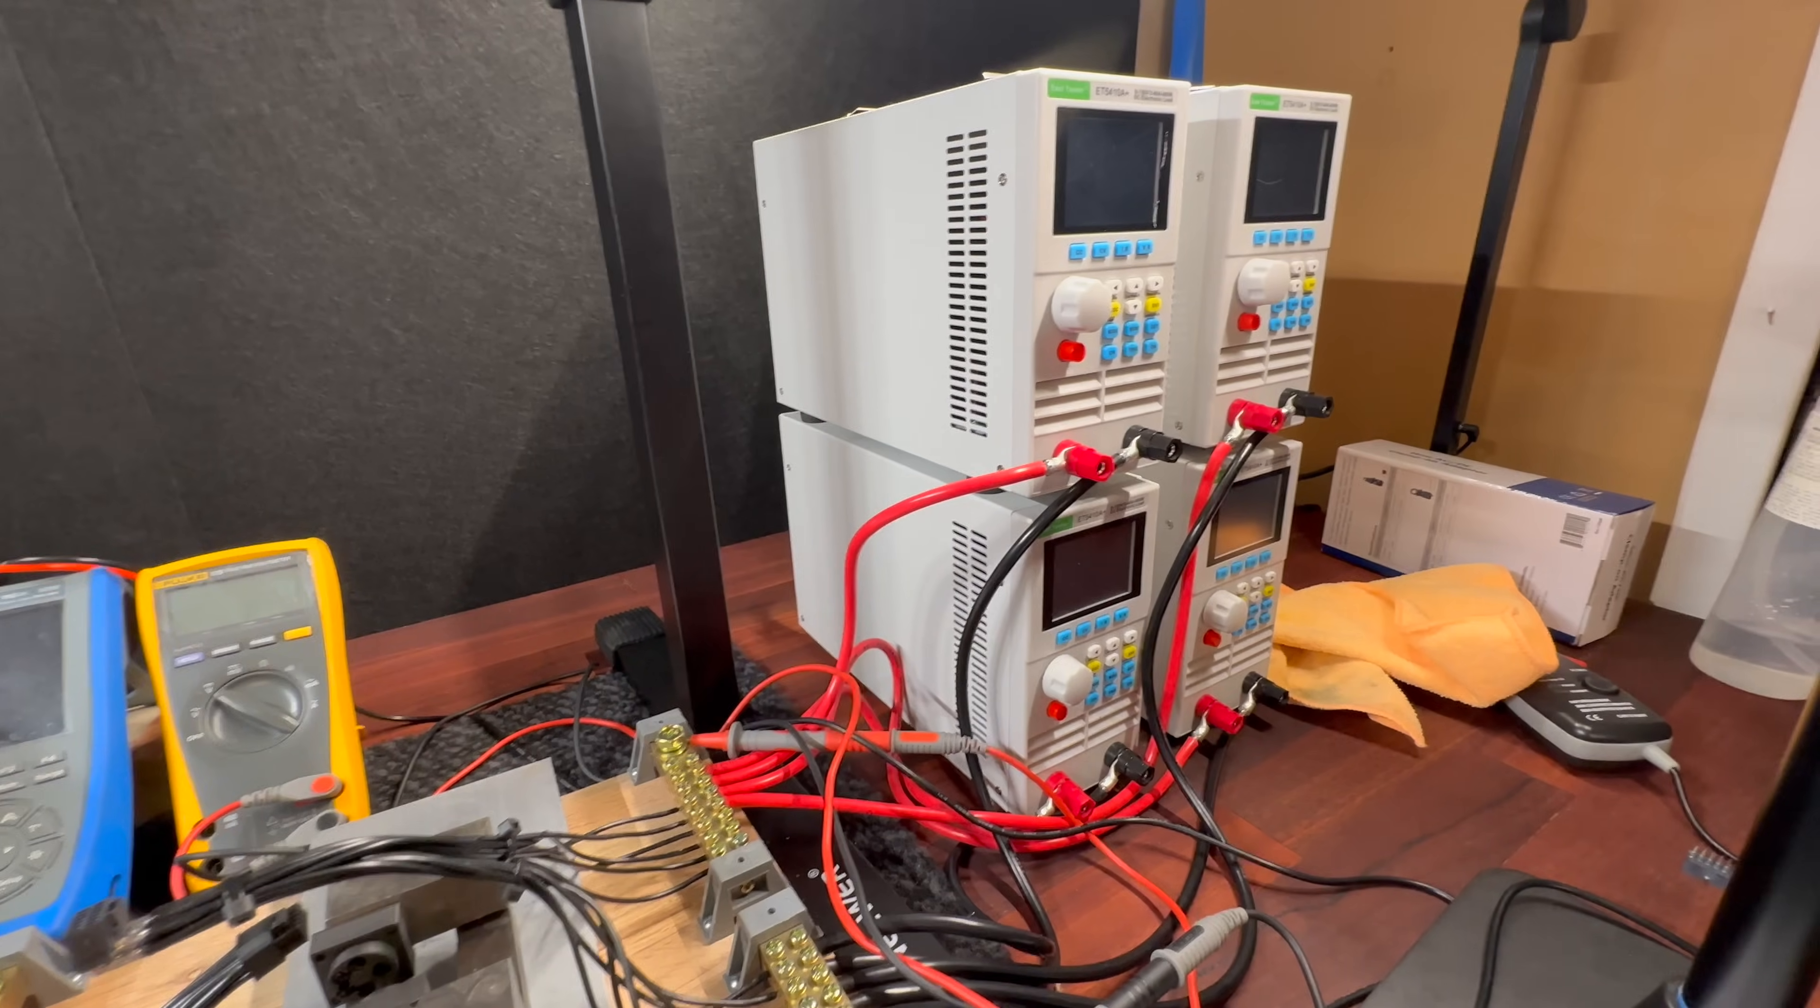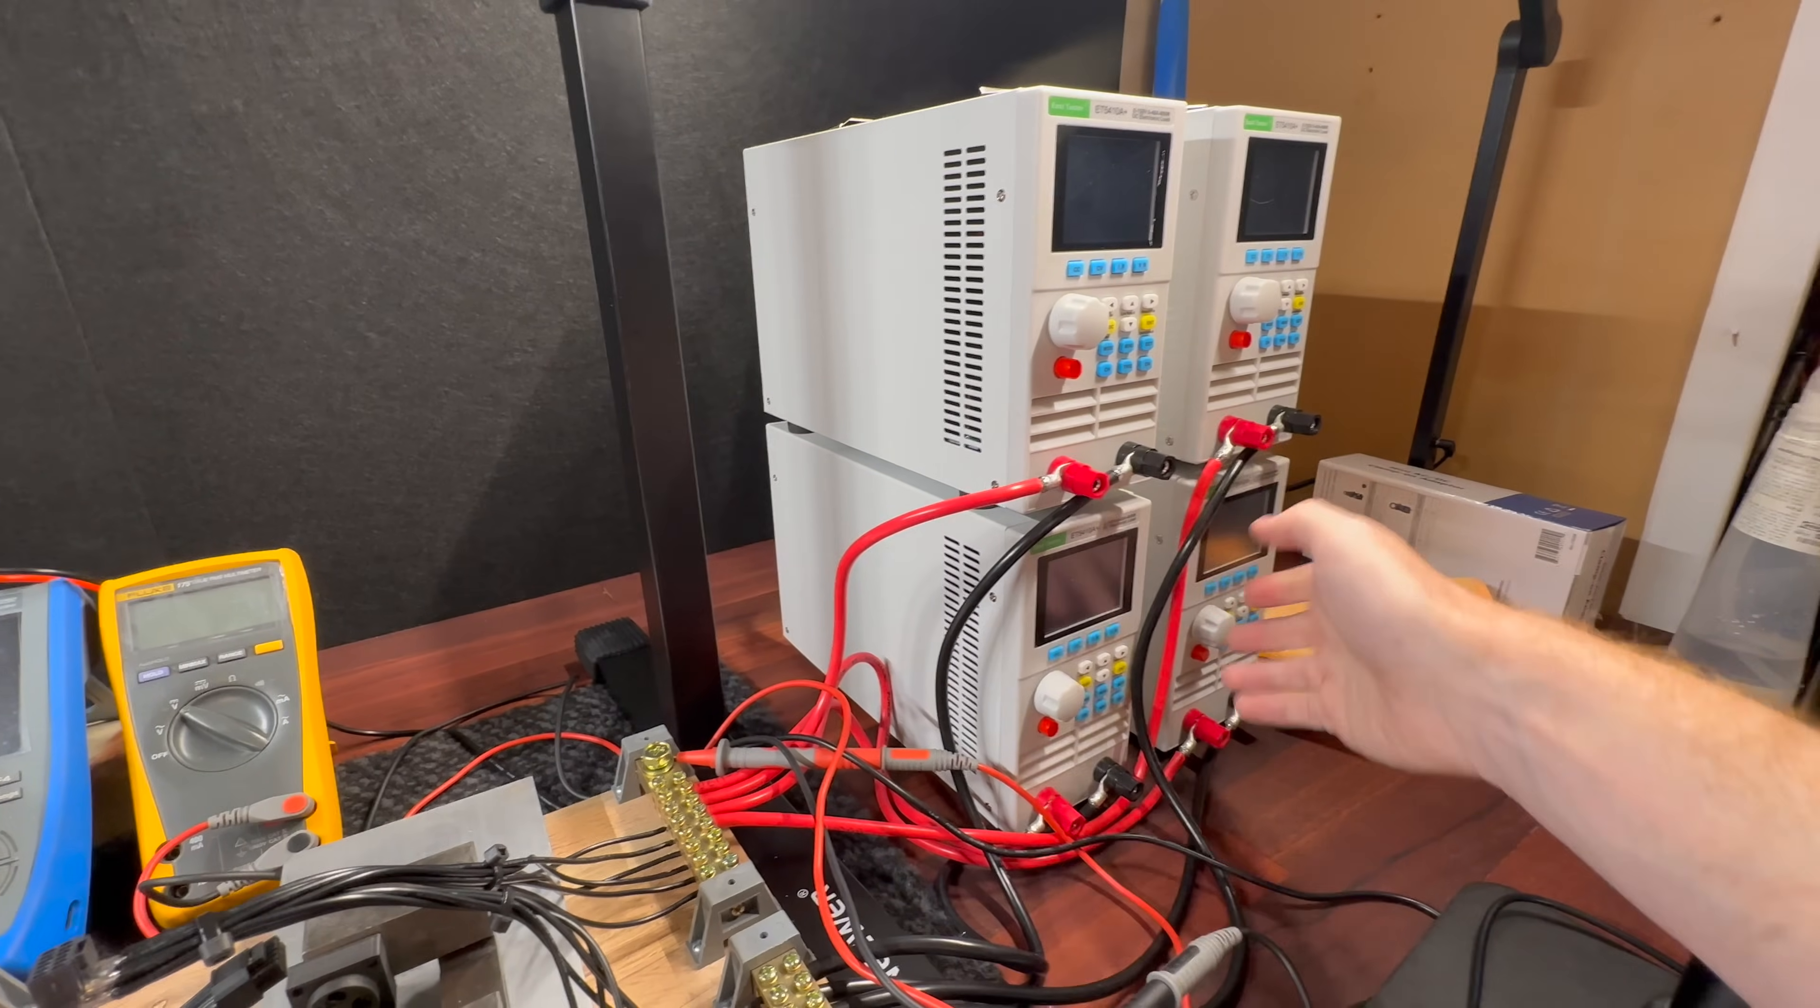In regards to the loads, we have 8 gauge wiring going to each of them. Eight gauge is rated for 50 amps, these loads are rated for 40 amps, so we have a little bit of safety margin on those wires. There's only one wire going to each of them, which is why it is 8 gauge instead of 12 gauge. I'm just doing this by the book and what the wire is officially rated for.